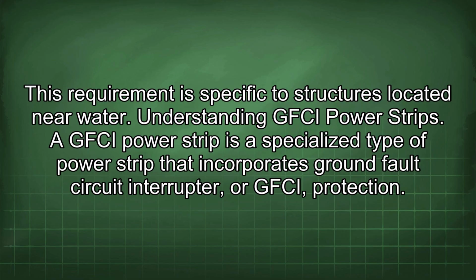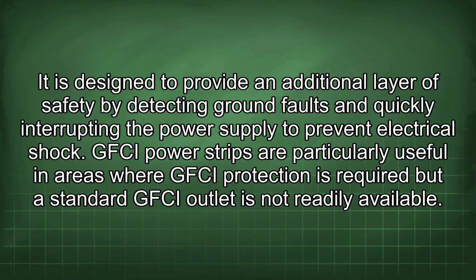This requirement is specific to structures located near water. Understanding GFCI power strips. A GFCI power strip is a specialized type of power strip that incorporates ground fault circuit interrupter, or GFCI protection. It is designed to provide an additional layer of safety by detecting ground faults and quickly interrupting the power supply to prevent electrical shock.